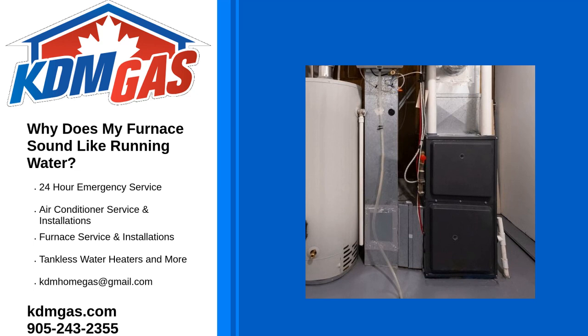Bubbling or gurgling. A bubbling or gurgling water sound coming from your indoor AC or furnace unit is usually an indication of a pressure issue. Improper internal pressure could be due to an overcharge of refrigerant, too much. It could also be the result of a refrigerant leak. Anytime the refrigerant level is incorrect, it causes an imbalance of pressure and air can get in where it shouldn't be, which in turn causes the bubbling or gurgling noise you are hearing. A trained technician will have the knowledge and equipment necessary to diagnose and repair the problem.